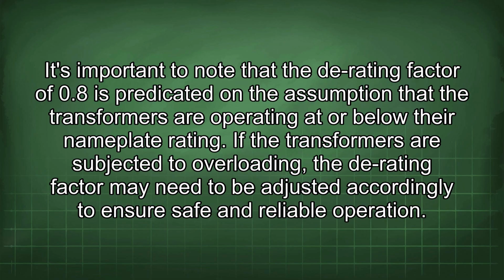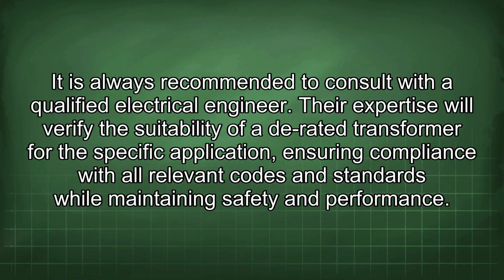It's important to note that the derating factor of 0.8 is predicated on the assumption that the transformers are operating at or below their nameplate rating. If the transformers are subjected to overloading, the derating factor may need to be adjusted accordingly to ensure safe and reliable operation. It is always recommended to consult with a qualified electrical engineer. Their expertise will verify the suitability of a derated transformer for the specific application, ensuring compliance with all relevant codes and standards while maintaining safety and performance.